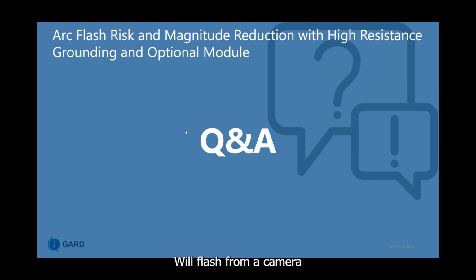Will flash from a camera trigger the arc flash module to trip a breaker? No, it will not, because we're looking for a particular spectrum of light.